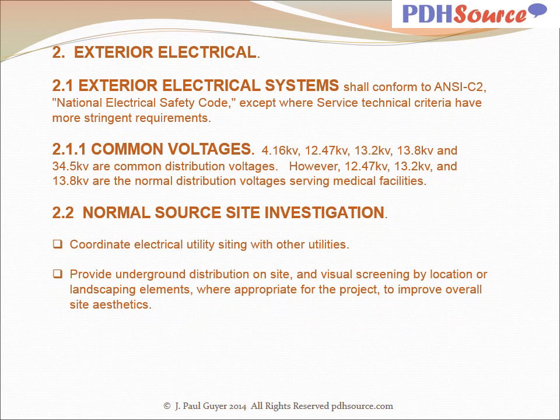Now some comments on exterior electrical. Exterior electrical systems shall conform to ANSI National Electrical Safety Code, except where service technical criteria have more stringent requirements. Common voltages for exterior electrical distribution are 4.16 kV, 12.47, 13.2, 13.8, and 34.5. However, 12.47, 13.2, and 13.8 are the normal distribution voltages serving medical facilities.